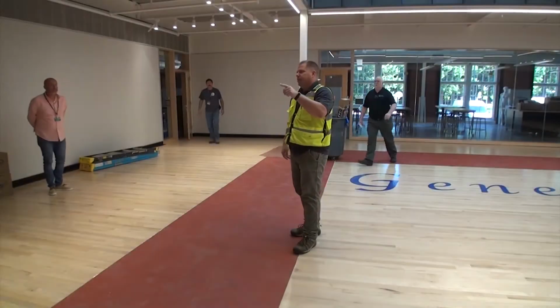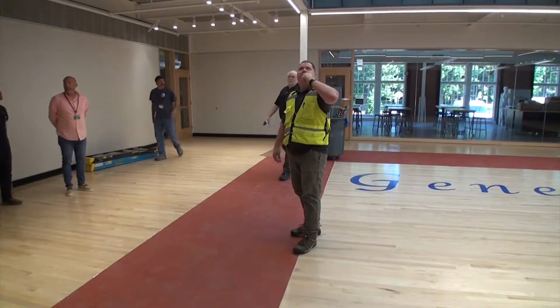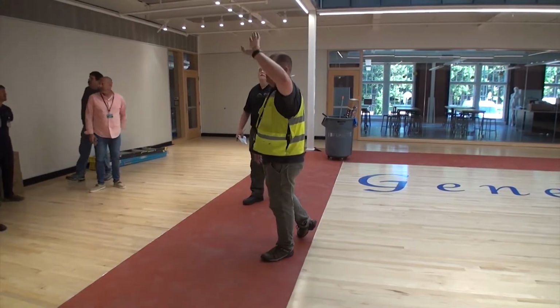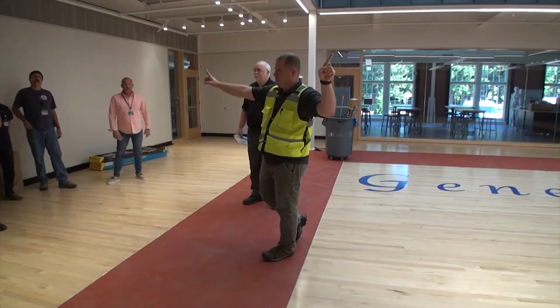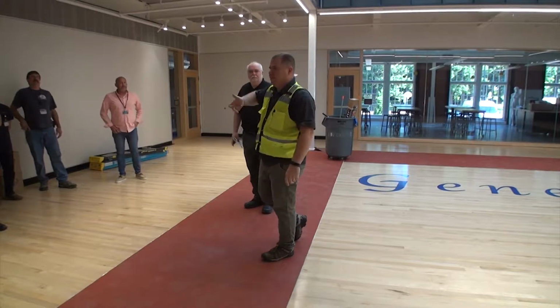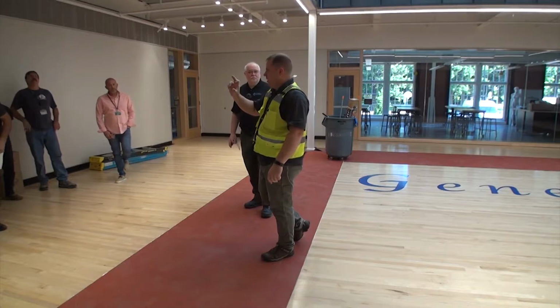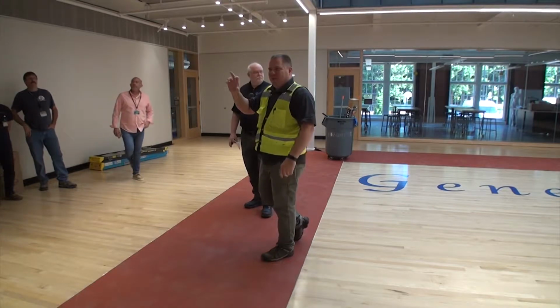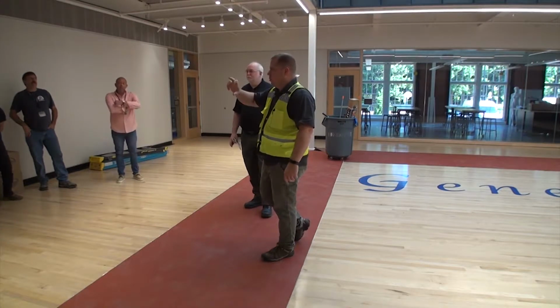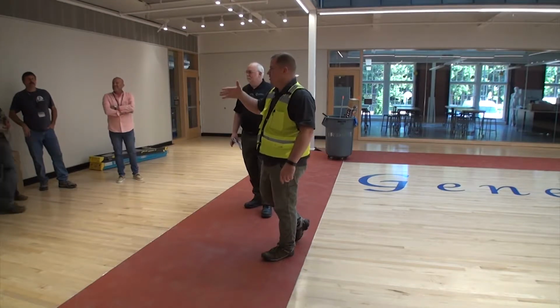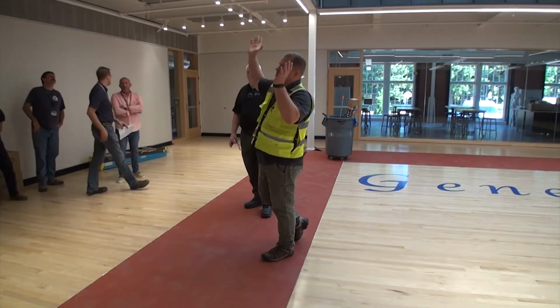Stairwells also have a different type of occupancy sensor. Instead of a ceiling mount, there's a wall mount. It's 180 degrees, it has an up and a down setting. It's mounted correctly right now, but if you take it off and put it back on, make sure you put it in the same orientation, or else the sensor will pick up the ceiling and not the floor.